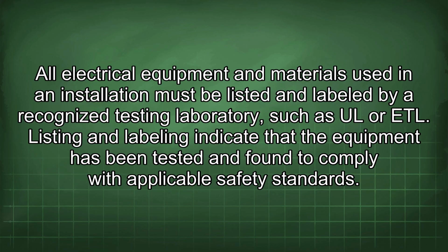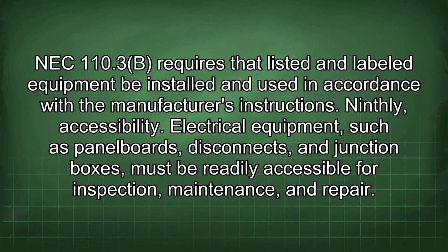All electrical equipment and materials used in an installation must be listed and labeled by a recognized testing laboratory, such as UL or ETL. Listing and labeling indicate that the equipment has been tested and found to comply with applicable safety standards. NEC 110.3(B) requires that listed and labeled equipment be installed and used in accordance with the manufacturer's instructions.